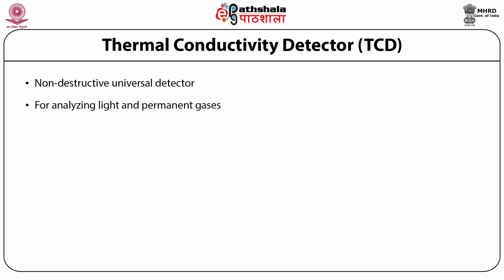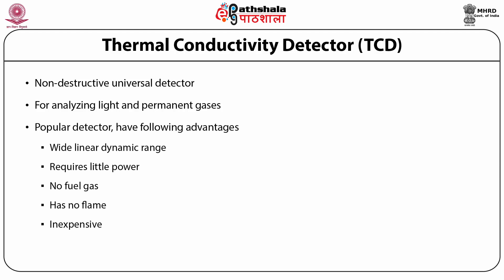Thermal conductivity detector is a non-destructive universal detector which is most commonly used for the analysis of light and permanent gases. Although it is one of the least sensitive gas chromatography detectors, it has advantages such as wide linear dynamic range, requires little power and no fuel gas, has no flame, and is inexpensive. Thermal conductivity detector is a popular detector and sometimes the only choice for few applications. It can be used in portable micro gas chromatographs as it can be easily miniaturized and run on low power consumption.